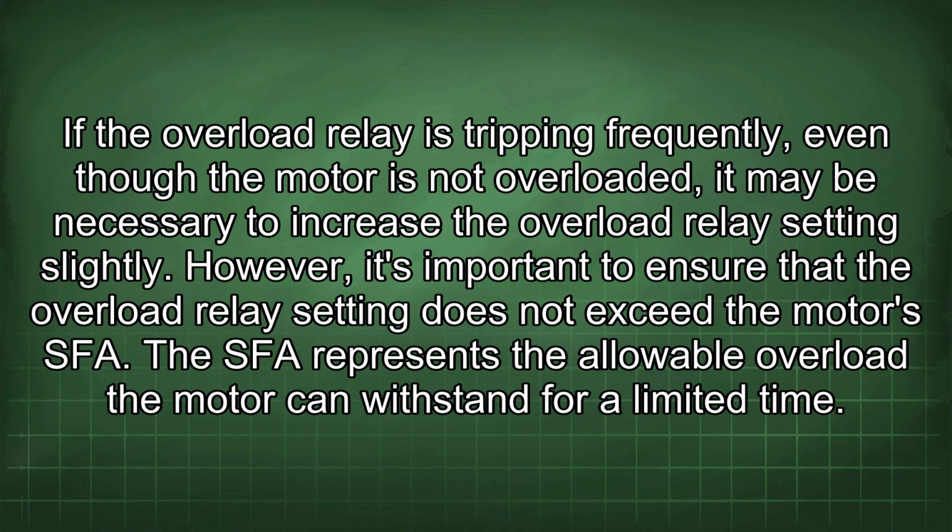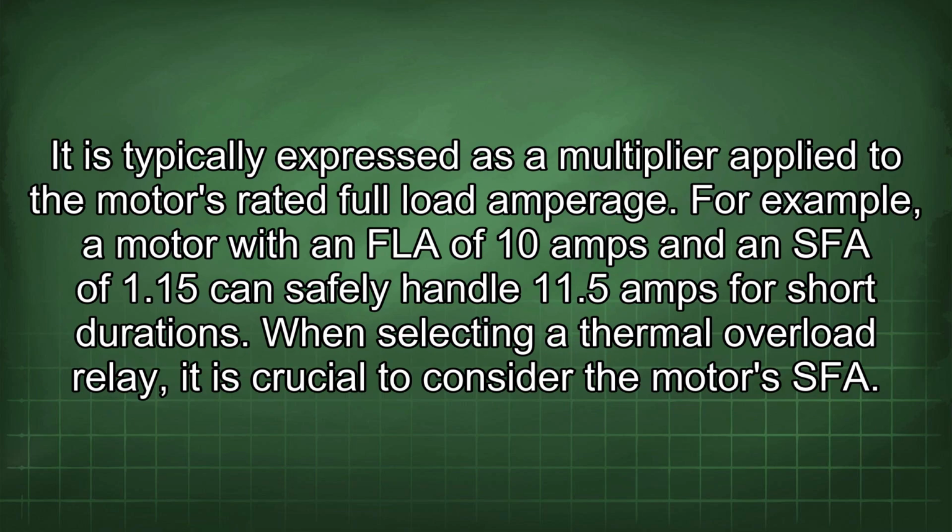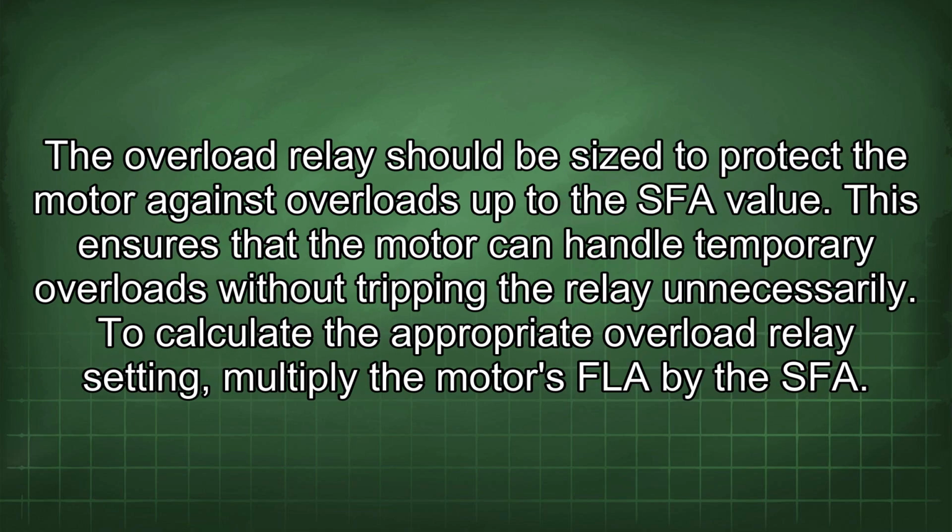The SFA represents the allowable overload the motor can withstand for a limited time. It is typically expressed as a multiplier applied to the motor's rated full load amperage. For example, a motor with an FLA of 10 amps and an SFA of 1.15 can safely handle 11.5 amps for short durations. When selecting a thermal overload relay, it is crucial to consider the motor's SFA. The overload relay should be sized to protect the motor against overloads up to the SFA value. This ensures that the motor can handle temporary overloads without tripping the relay unnecessarily.